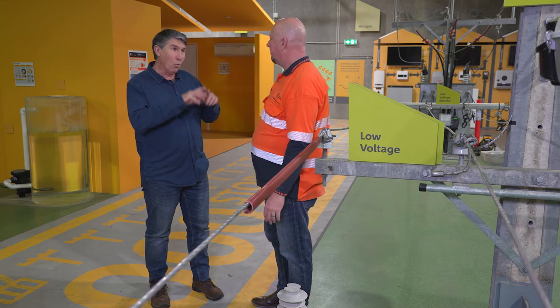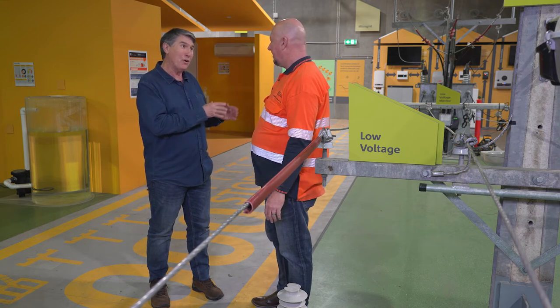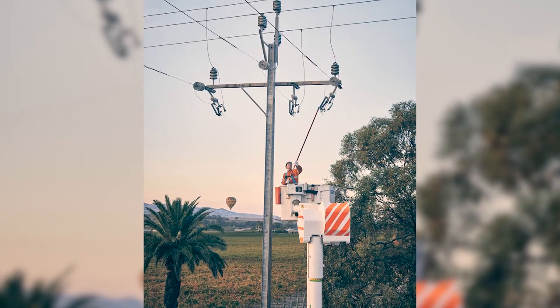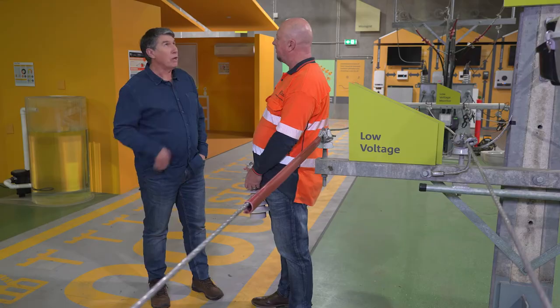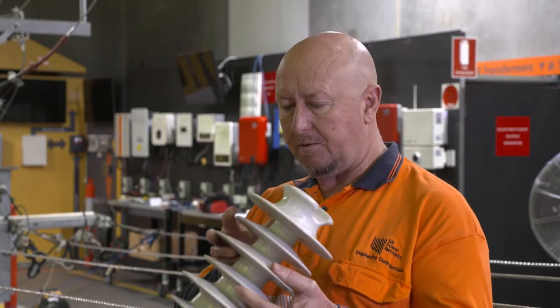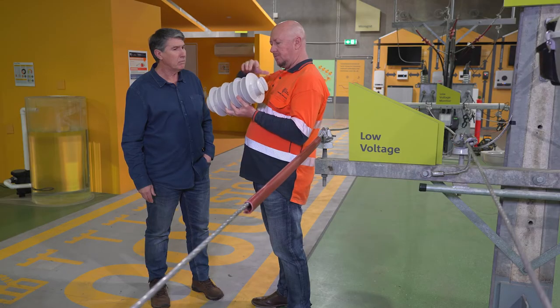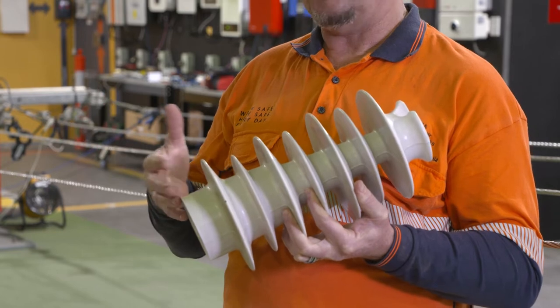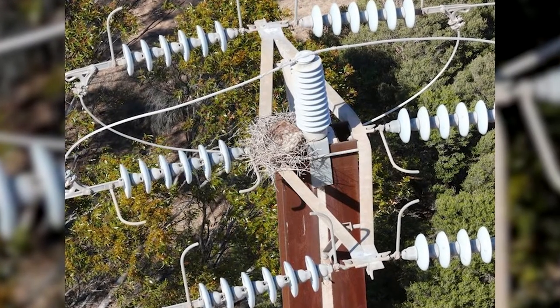It's amazing that with all of that, the power does go back on in a relatively short period of time. We can actually zoom in on where the lightning has occurred near our power lines to better position our crews into those locations first. So how are you reducing the damage to those porcelain insulators? We've been proactively replacing the porcelain insulators with resin insulators. The lightning will strike across the face of the insulator and we'll only have a momentary interruption of about two to five seconds to our customers, and the power will remain on so we don't have to go out there.